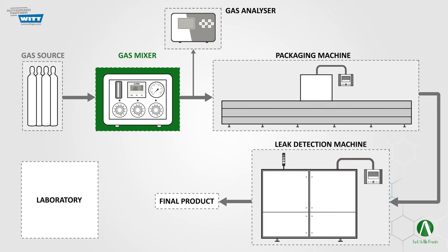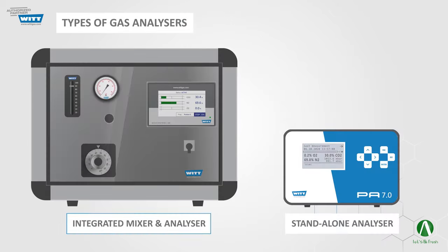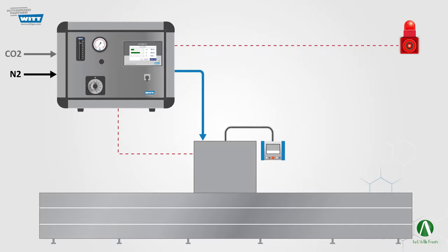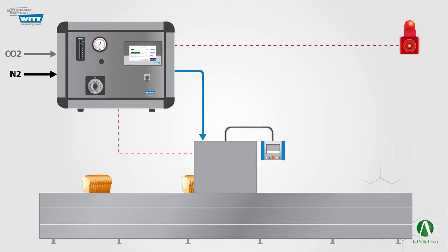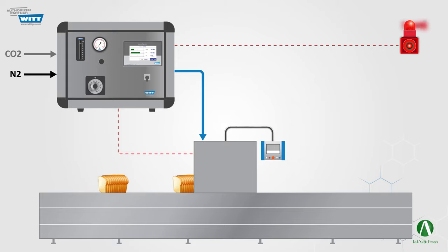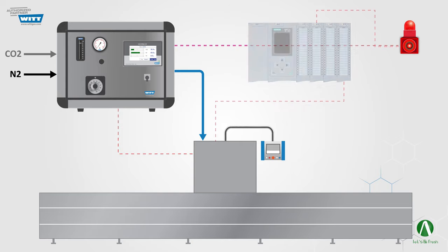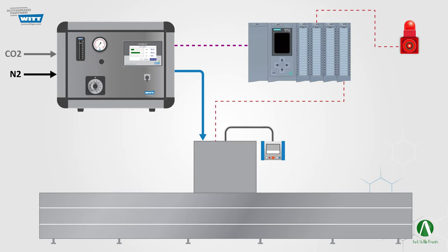The next component is the gas analyzer, which could be integrated into the gas mixer or used as a standalone unit for monitoring the exact real-time percentages of the gases. Equipped with measurement sensors, the analyzer works in conjunction with the mixer, and in case of any anomalies in the gas mixture, it will inform the operator through activating an alarm, or will directly shut down the whole or a specific part of the system. The analyzer can be connected to a PLC as well and integrated into the main control system.